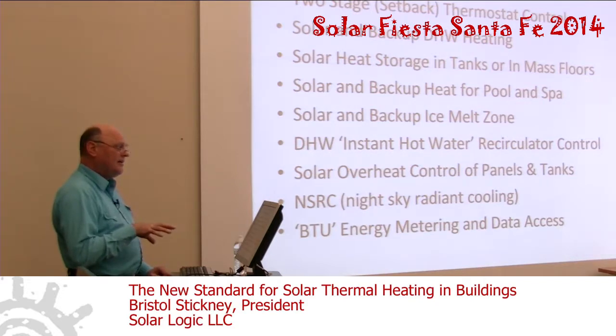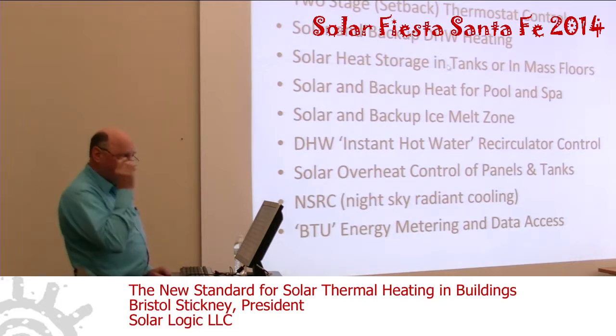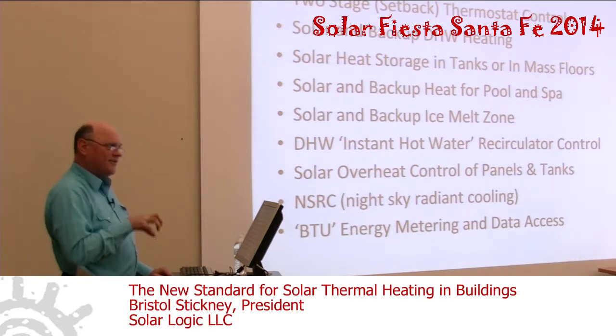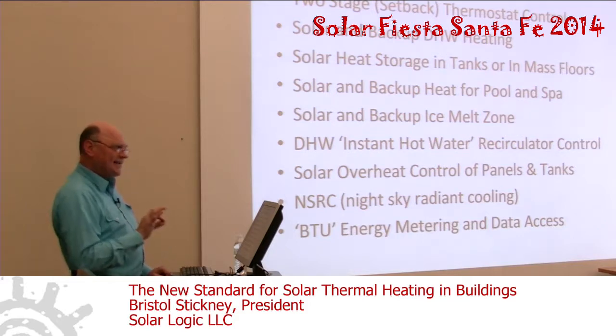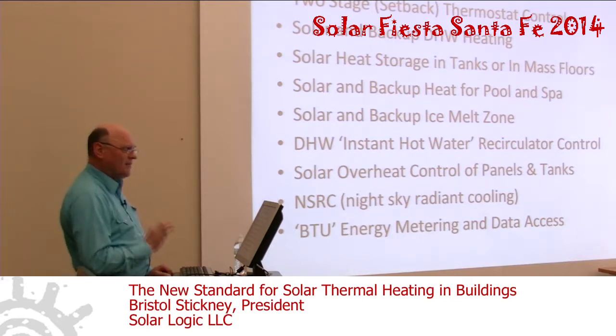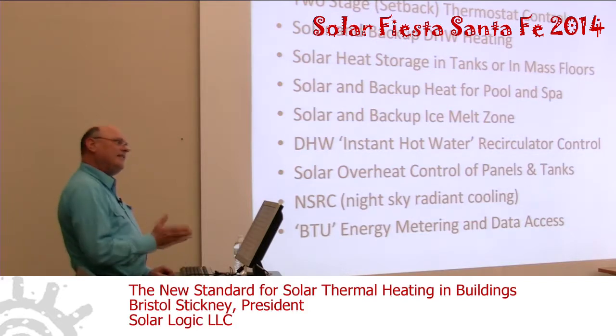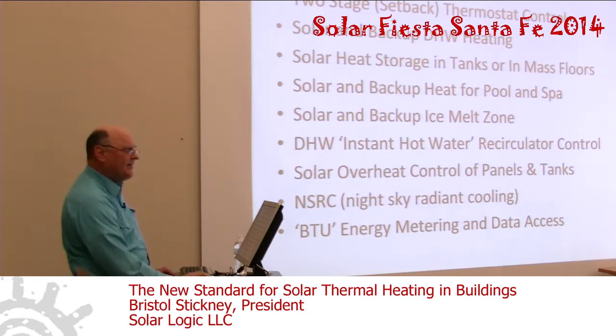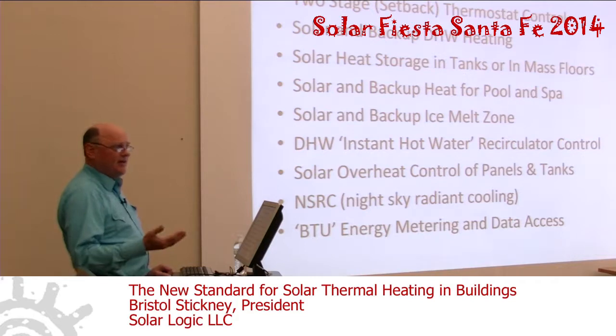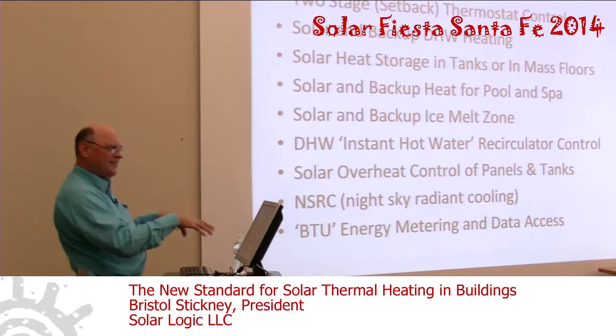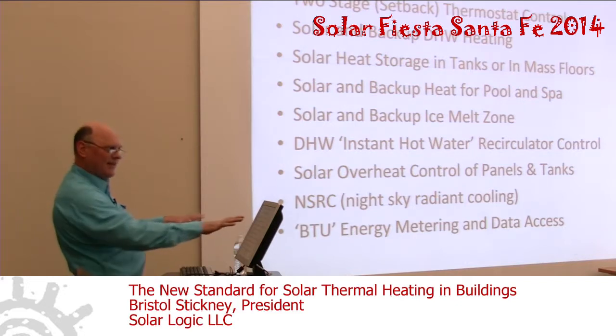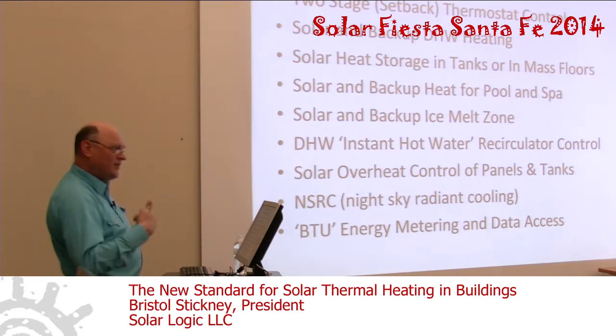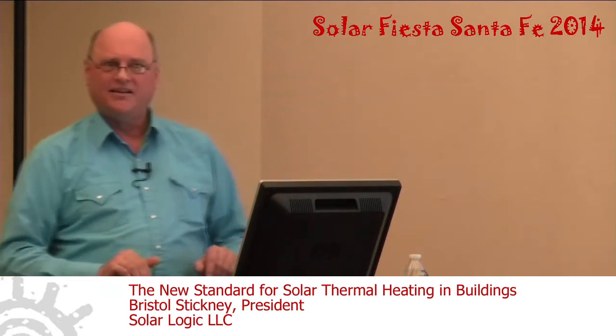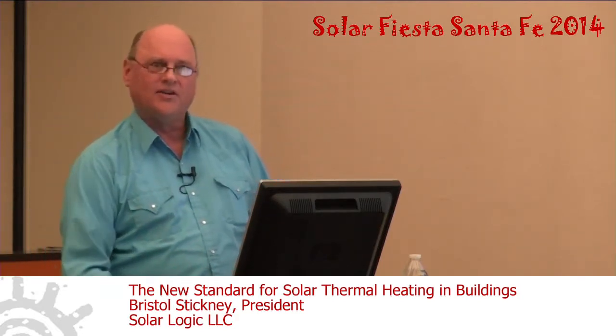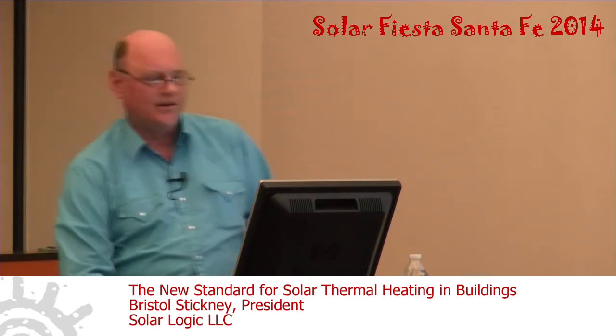This is something that we've pioneered here at Solar Logic in Santa Fe, the heat storage directly in concrete floors, and we have got it down to a system. We can make it work beautifully, and we can eliminate the need for very large water heat storage tanks by using the heat storage in the floor. This is actually done all the time in passive solar buildings. The sun shines in a passive solar building and the heat is absorbed by the concrete floors and the adobe walls. Well, we're doing this actively now. We're delivering heat to the concrete floors and controlling the heat storage in the floors to be a comfort temperature.